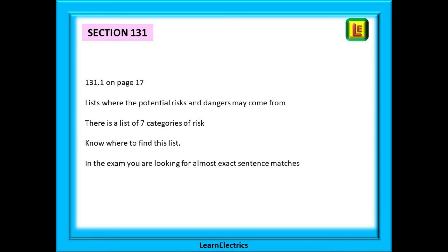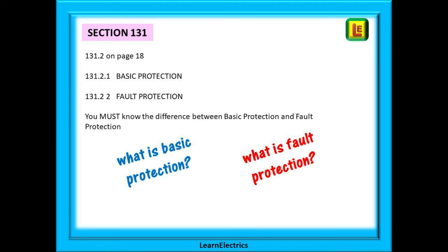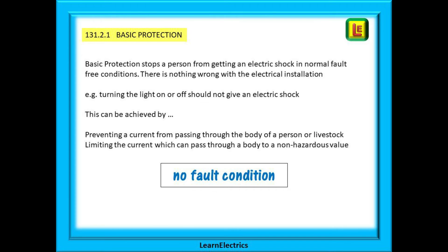Regulation 131.1 gives us a list of risks that might exist, and exam setters love lists. On page 18 we find two very important regulations frequently asked as exam questions. They cover basic protection and fault protection. Regulation 131.2.1 — basic protection — stops a person from getting an electric shock in normal, fault-free conditions. The regulation states this can be achieved by preventing a current from passing through the body of a person or livestock, or by limiting the current which can pass through a body to a non-hazardous value. For example, turning a light on or off should not give an electric shock because the switch cover provides basic protection.